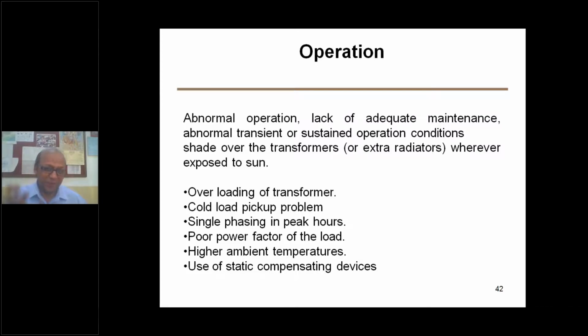So you switch on slowly, otherwise the transformer will fail. This is also a problem to be considered. Wherever it appears, it is more prominent in posh colonies, where there are thermostatically controlled devices like geysers and ACs — a very serious problem there. Single-phasing, no doubt, happens in peak hours, so you have to take care.